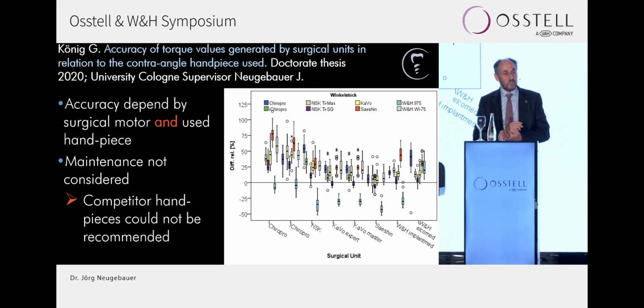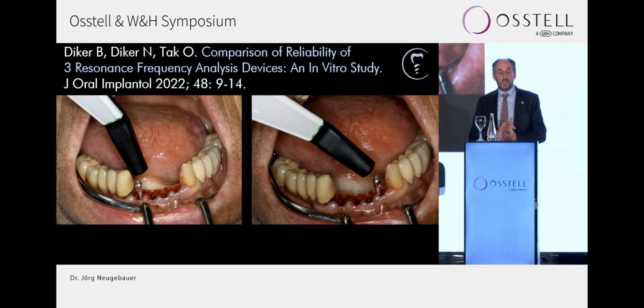We also have to check the maintenance of these devices, because if they are not cleaned enough, the measurements could be even worse. So if you would like to measure the insertion torque, you always have to stay in one system, with one motor and the corresponding handpiece, so that you get the best values. In our study, we saw that the most appropriate measurements were done with the Implantmed motor and the W&H handpiece. The other opportunity, as already mentioned, is the use of the Osstell device.